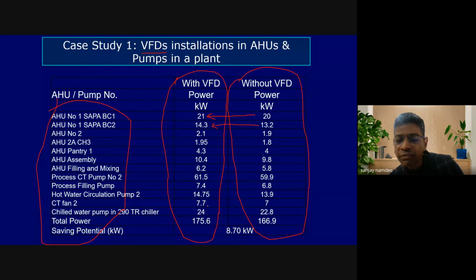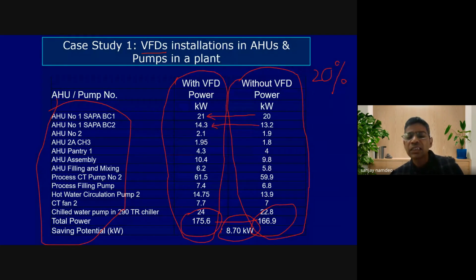Here you can see that with VFD, the power has slightly gone up. In total, if I see the difference across all this equipment, with VFD the power is around 175.6 kilowatt, and without VFD it is 166.9 kilowatt. So industry's perception is what? That they have reduced 20%. But what is the actual situation? The power consumption has increased by this factor, around 8.7 kilowatt. Whereas VFD is versatile equipment and definitely gives savings, in this case it is not giving savings.